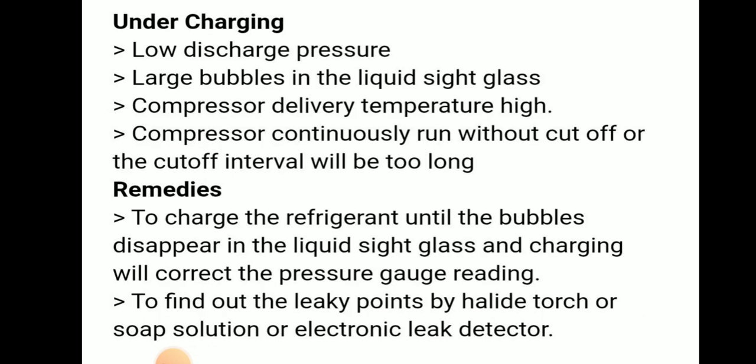Undercharging symptoms are: low discharge pressure, large bubbles in the liquid sight glass, compressor delivery temperature high, and compressor continuously runs without cutoff or cutoff interval will be too long.